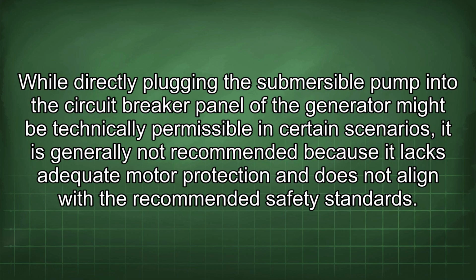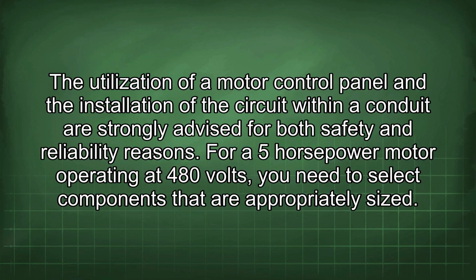While directly plugging the submersible pump into the circuit breaker panel of the generator might be technically permissible in certain scenarios, it is generally not recommended because it lacks adequate motor protection and does not align with the recommended safety standards. The utilization of a motor control panel and the installation of the circuit within a conduit are strongly advised for both safety and reliability reasons.